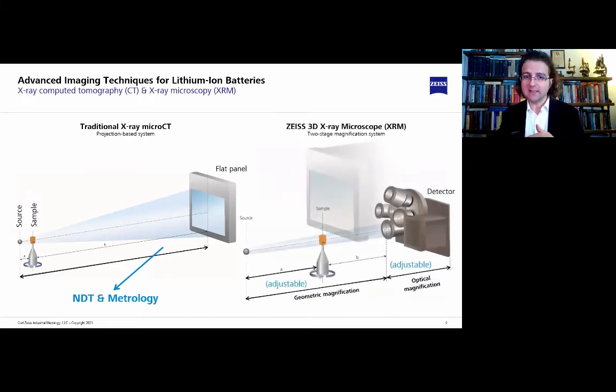The main difference of the so-called X-ray microscopes as compared to the traditional projection-based micro-CT system is that they include a set of lenses that add optical magnification capabilities, additional to the geometrical magnification. This allows submicron resolution capabilities. With the traditional X-ray CT system, it is difficult to achieve that. Projection-based systems are typically limited to resolutions in the order of 2 microns or 5 microns in the best possible conditions for very small samples.